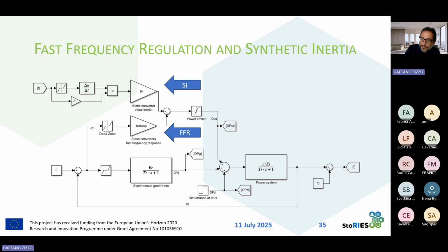And so the same system that we examined before, where we have synchronous generators, the natural response of the power system, if we include batteries participating in frequency regulation and providing synthetic or virtual inertia, can be represented in this way. We have here the frequency variation that is sent to the converter to which the battery is connected, and thanks to this gain, a power is injected into the grid proportional to the frequency variation.